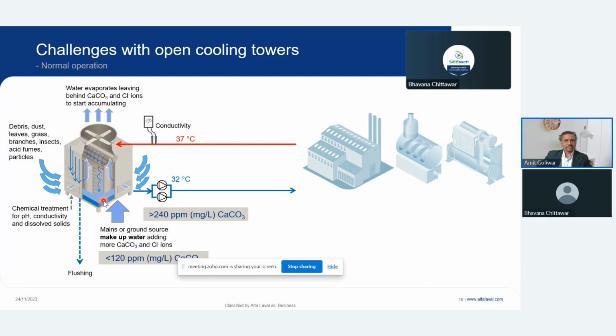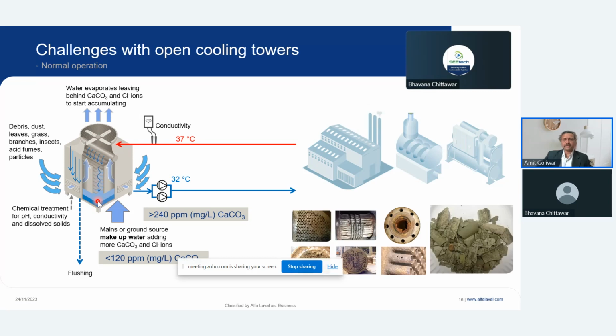So when it goes up, what we normally do is add chemicals. Even after adding chemicals, we realize that the water TDS is very high. So we flush and add makeup water. This is the way we maintain the calcium carbonate content in cooling tower water. But even after that, we end up with such kinds of scales. And there are typical areas, coastal belts, where it is very difficult to get water. The groundwater itself will have 800 plus TDS.